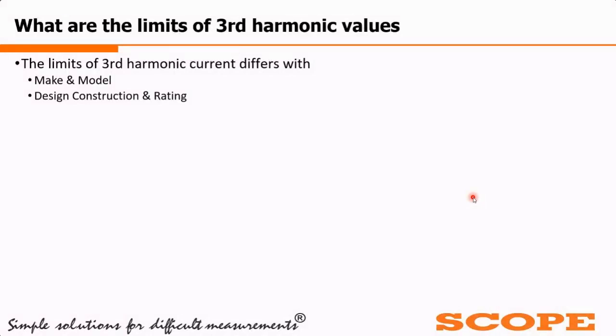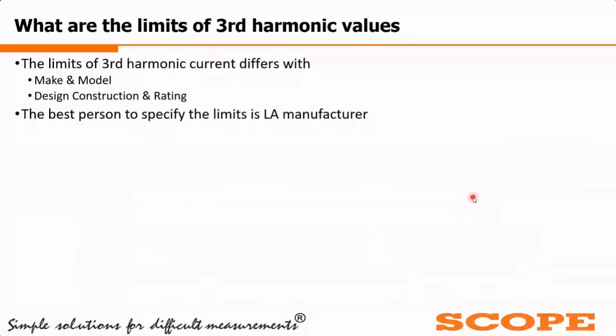value as such. They have also talked about the trending of the data, but some of the utilities are following some data. Obviously, the best person to specify this limit is the LA manufacturer, because they know their construction, they know what kind of ZnO blocks they are using and what their characteristics are. So they are the best person to specify the values. So ask the LA manufacturer to specify the limits in the test report. You mention the resistive current as well as the third harmonic percentage in your test report.